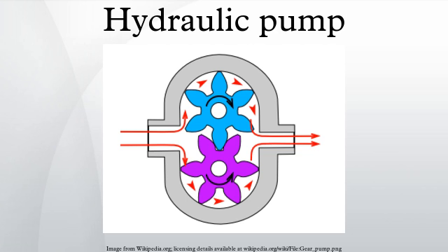In case of statics, hydraulic pump types, gear pumps are simple and economical pumps. The swept volume or displacement of gear pumps for hydraulics will be between about 1 and 200 milliliters. They have the lowest volumetric efficiency of all three basic pump types.